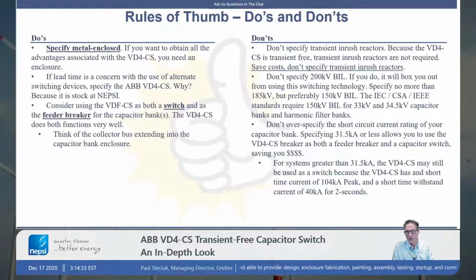If lead time is a concern with the use of an alternate switching device, specify the ABB VD4-CS. Why? Because it's stocked at NEPSI. We stock this switching device. Consider using the VD4-CS as both a switch and as a feeder breaker for capacitor banks. The VD4-CS does both functions very well. I often say, think about the collector bus, which commonly picks up your collector system cables. Consider that flowing into the capacitor bank, picking up a couple more breakers, 1, 2, 3, or 4 breakers that pick up capacitor stages. They can be considered breakers and switches. So you can eliminate the upstream feeder breaker that commonly feeds those capacitor banks.